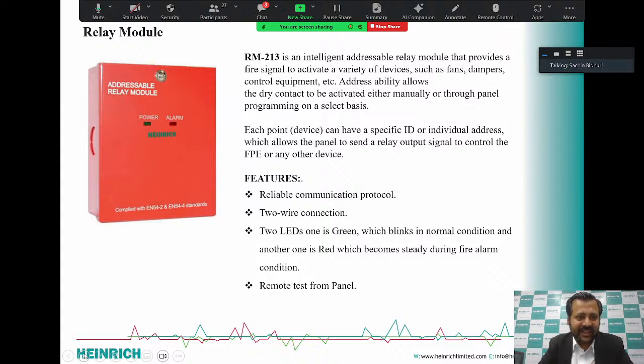Relay module: basically, these are used for integrating other solutions with the fire alarm system. For example, a relay module is used for integrating a PA system with the fire alarm system, and you can have zone-wise integration as well as loop-wise integration. These modules are used for integrating different types of other solutions with fire alarm, like the control module. We have HVAC, which you can integrate with the fire alarm system. With this addressable relay module, you can integrate a PA system. So these are the different modules required to integrate the fire alarm system with other solutions.